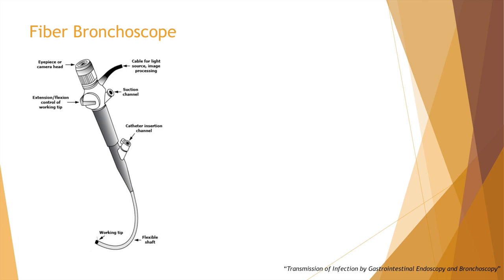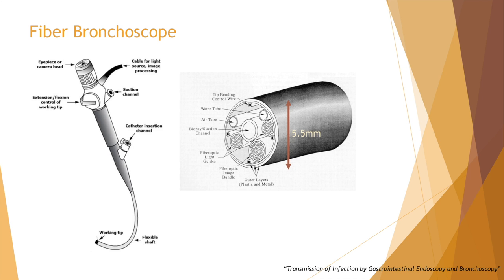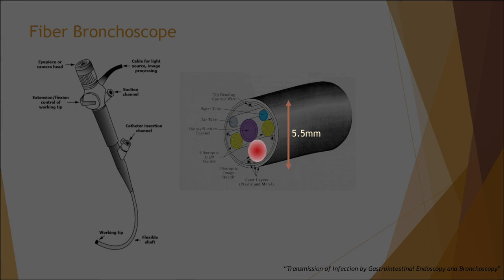A fiber bronchoscope has primarily two parts: the eyepiece where doctors can look into, and the objective that goes inside the patient's airway. The distal end has an illumination channel and the main imaging channel. For more advanced bronchoscopes, there are respectively channels for water, air, a channel to perform biopsy, illumination, and lastly the imaging channel that is connected using optical fibers. This is the part we will be focusing on for the rest of the video.